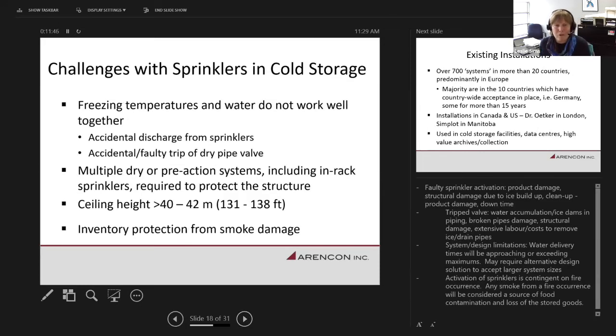We know the challenges of sprinklers in cold storage. You know, freezing temperatures and water are not going to work well together. Accidental discharge, whether it's bumped by material handling, failure of the sprinkler mode, even a trip of the dry pipe valve. We get water in the pipes if it's either discharged from the sprinkler or it's even contained in the pipes. We tend to get a lot of ice loading on the materials or within the pipe.